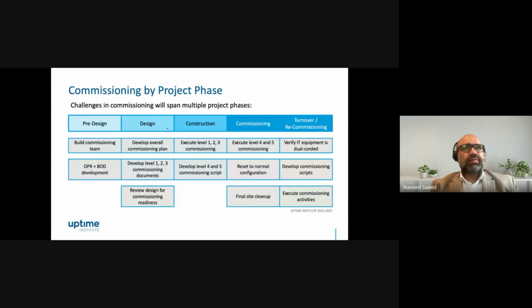Commissioning by project phase remains the same, but it's very important that during the pre-design and design phases, when you have selected a specific kind of liquid cooling, you develop an overall commissioning plan, develop level 1, level 2, level 3 commissioning documents, and review your design for commissioning readiness. That's very important: that you have the proper tap-offs, where you're going to put the load banks, how you're going to connect the load banks, and what level of commissioning, what kind of rigor, you want your facility to be done to. Because nobody wants to test their $40,000 GPU on an uncommissioned facility. It doesn't make sense. So it's really, really important for data center infrastructure professionals to make sure that the facility is properly commissioned before it is handed over to IT for turnover. Otherwise, the issues from the commissioning are going to pop up during the operations of IT equipment.